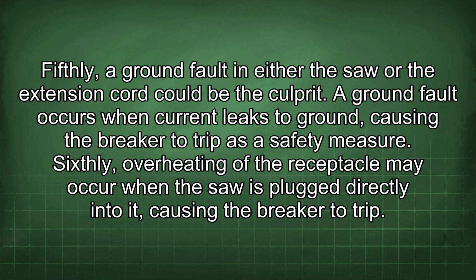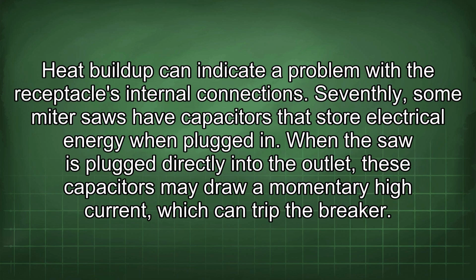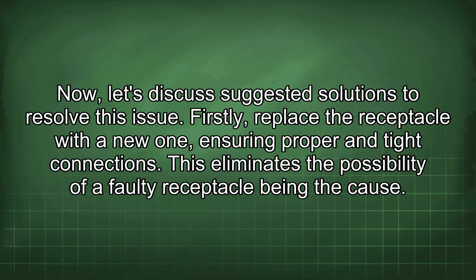Sixthly, overheating of the receptacle may occur when the saw is plugged directly into it, causing the breaker to trip. Heat buildup can indicate a problem with the receptacle's internal connections. Seventhly, some mitre saws have capacitors that store electrical energy when plugged in. When the saw is plugged directly into the outlet, these capacitors may draw a momentary high current, which can trip the breaker. Now, let's discuss suggested solutions to resolve this issue.